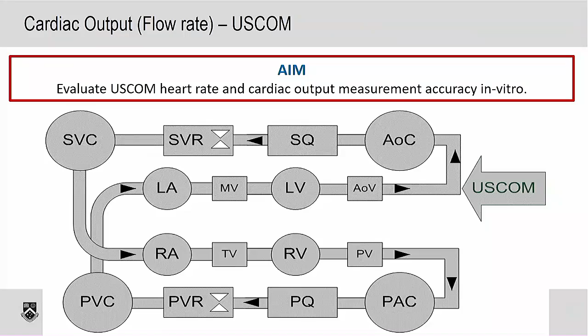Okay, so again, we randomly adjust the cardiac output, in this case between 2 and 10 litres per minute, because we know this sensor is meant to have quite a large range. I said before about 0.1 to almost 20 litres a minute. We blinded the physicians again. We asked them to determine, in this case, 9 different cardiac output settings that we randomly changed. We were changing things like heart rate and blood flow as well. This is particularly useful because the USCOM can be used to measure heart rate as well.